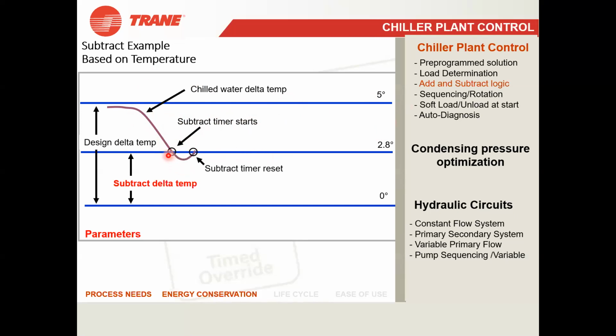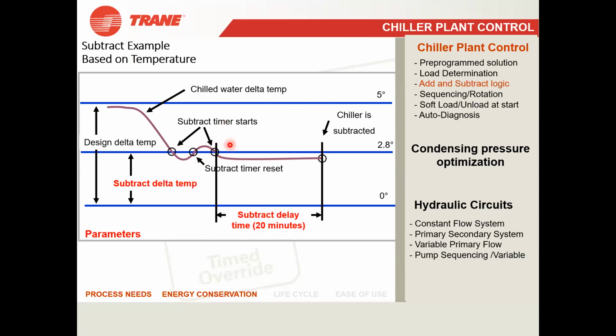Again, it will not be stable; it will be fluctuating. Whenever it reaches this 2.8 degrees, it will start the timer, and you can visualize that sitting in your control room. When it subtracts one chiller, or switches off one chiller, your controller can see that for 20 minutes the delta T is at 2.8 degrees. That means my load has been reduced, so I have to cut off a chiller. Then it will switch off one chiller.